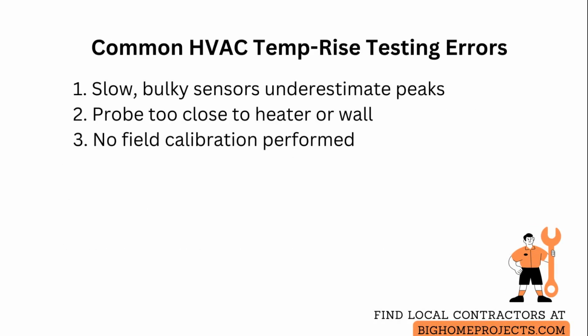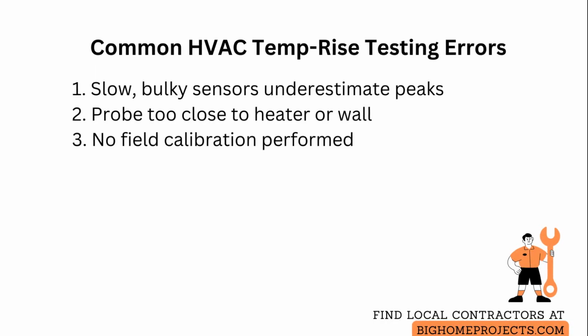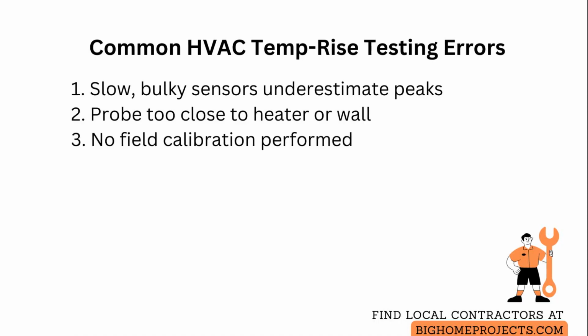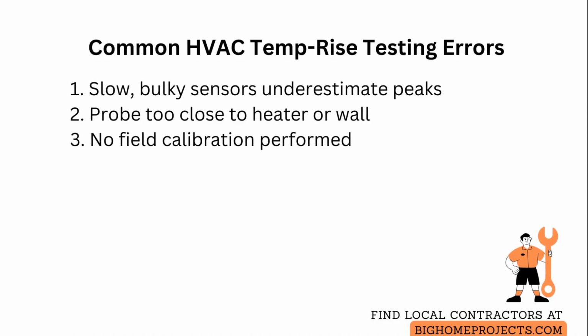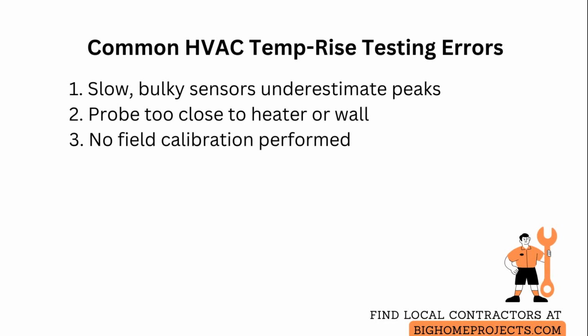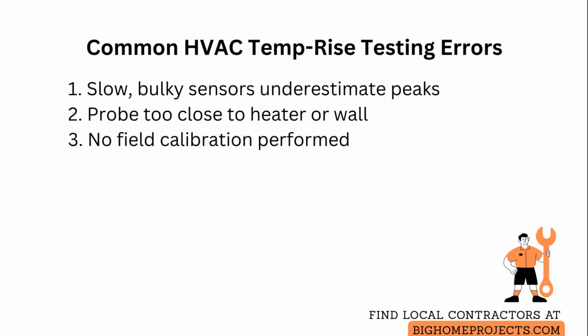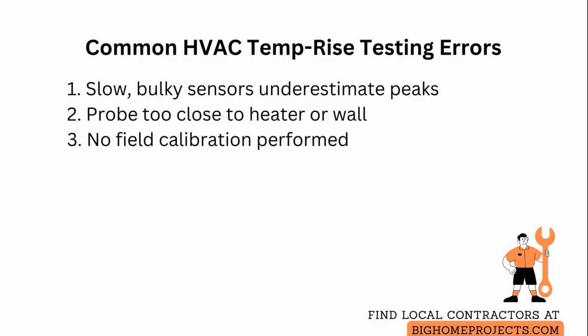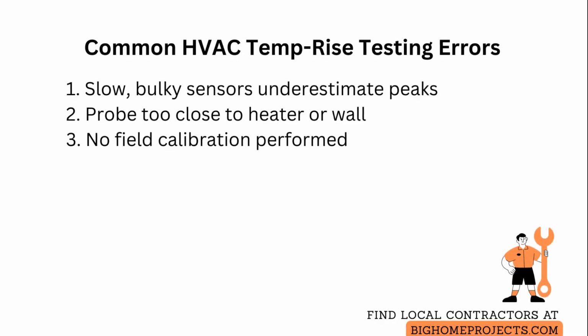Common mistakes include using slow, bulkier sensors that average transient fluctuations and understate the true peak temperature rise. Fix this by switching to bead thermistors or fine-gauge thermocouples with known response times. Another frequent issue is placing the probe too close to the heater or duct wall where radiant heat or conduction skews results. Correct placement by centering the junction in the airflow and securing it away from reflective surfaces.